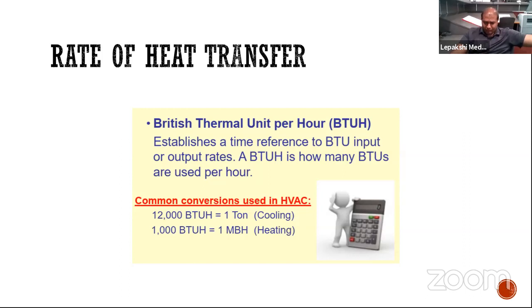When talking about the cooling side, when making load calculations to determine the cooling load, you don't mention units in BTUH. You talk in tons. For instance, for an air conditioner or chiller, you'd say I need a 5-ton or 10-ton chiller, not a 50,000 BTU chiller. It's just common terminology, so for cooling we'll stick with tons.